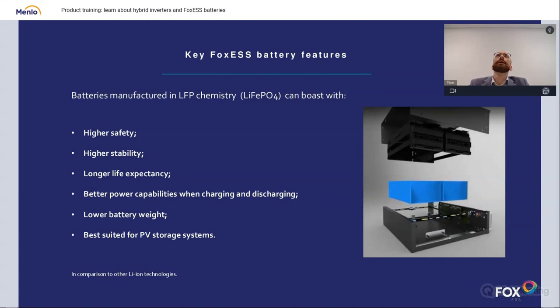Lithium iron phosphate batteries, first of all, are safe. They don't spontaneously combust. They don't explode. They don't degas. They can be charged and discharged with high amounts of current. Their life is really long. The chemistry is really resilient to changes. The batteries weigh less than lead acid batteries, of course, but that doesn't mean that those modules are light. Every such module weighs about 30 kilograms. It's full to the brim with cells.